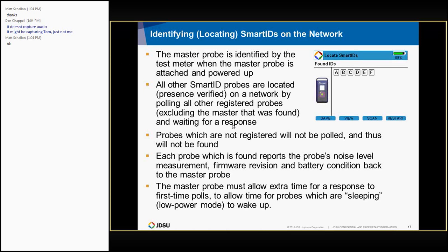And then when you start the locate IDs test, after the master probe is identified, the master will then poll all the other probes that you have registered and find out which ones are out there and what frequency is best to talk to the probe. We'll check for 3 different frequencies to talk to the probe, and basically just put up a list of everything that it found. Probes that are not registered will not be polled. So if you attach an unregistered probe to your network and turn it on, it might be there and capable of responding, but since it's never polled, it will never be found.